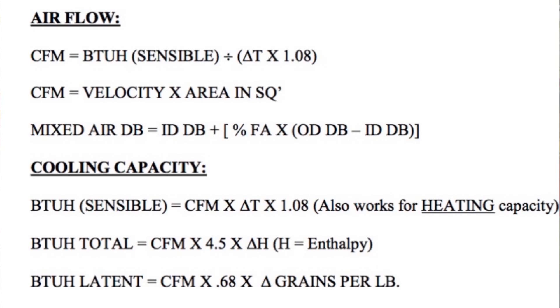If you go into a job measuring enthalpy in and out across a coil and the delta H is higher than 6.67 — say 7.5 or 8 — you could have a low airflow situation. You'd then measure CFM and it might come out at 350 or 325 CFM per ton, and you can make adjustments if possible. Similarly, a relative humidity in the comfort zone of 50–55% should correspond to a sensible temperature split of 18–20°F across the coil. If it hits 22–23°F, there's likely an airflow issue.